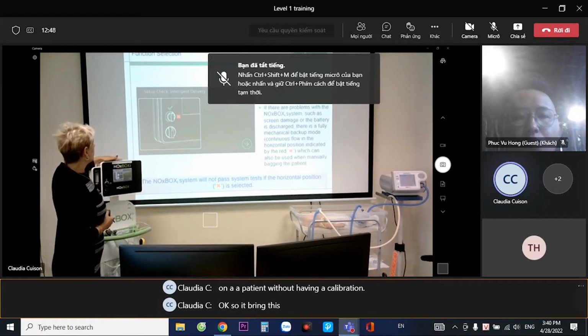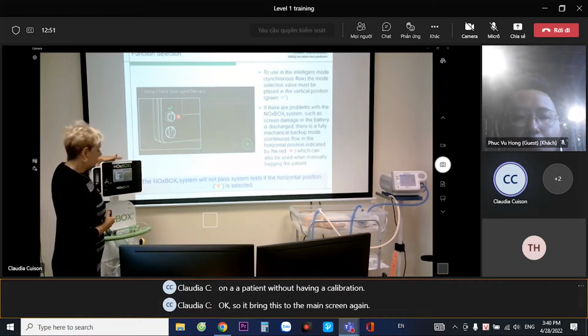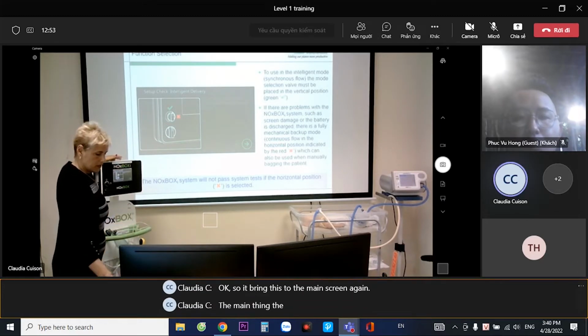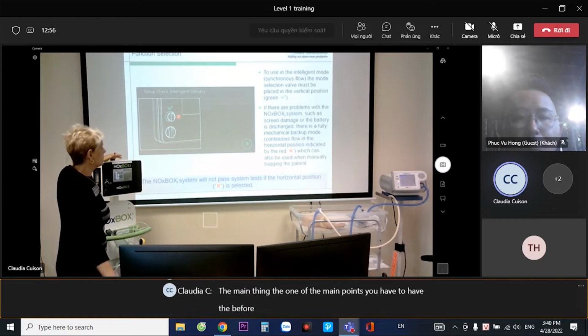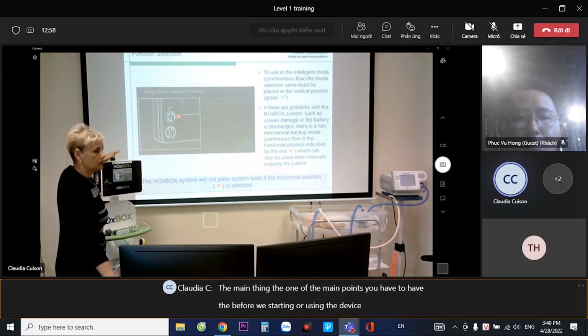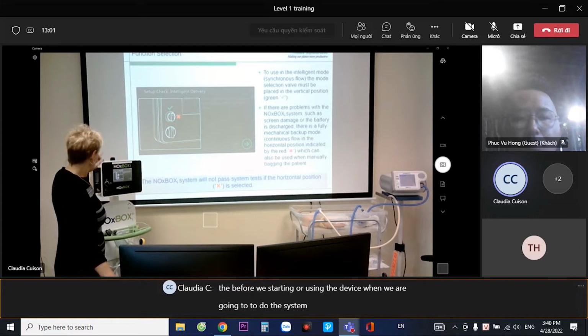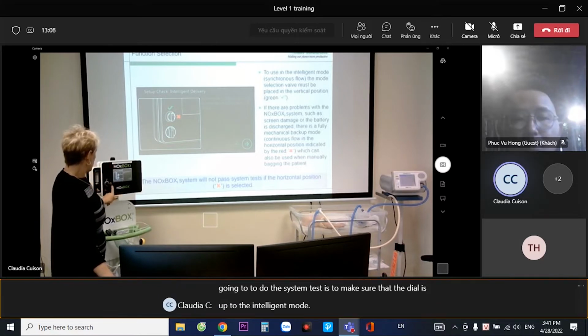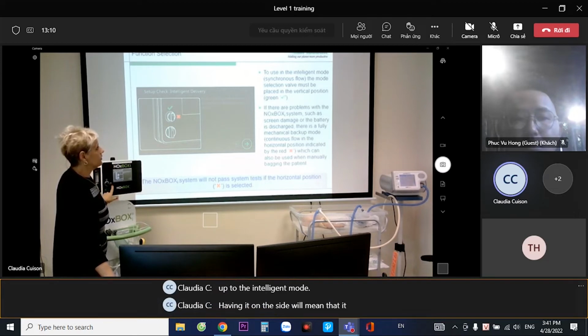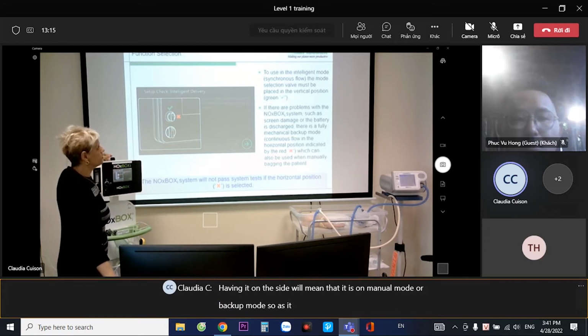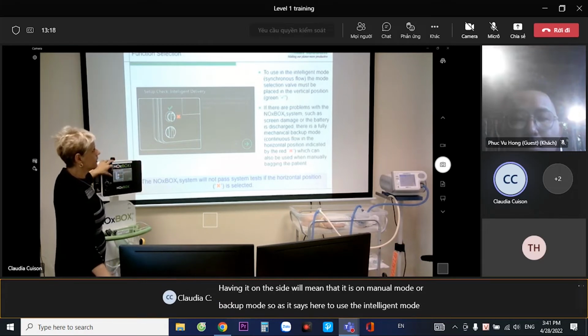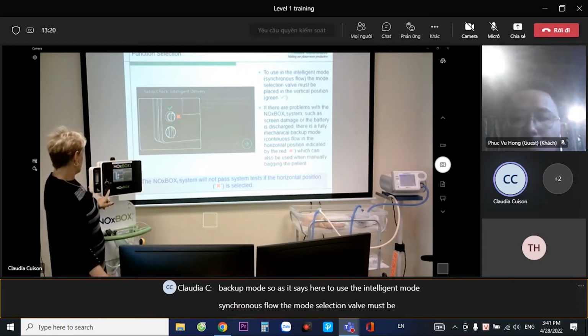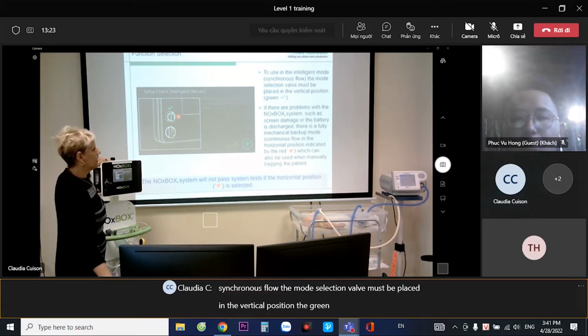Okay, so it brings us to the main screen again. One of the main points you have to check before using the device, when we are going to do the system test, is to make sure that the dial is up at the intelligent mode. Having it on the side will mean that it is on manual mode or backup mode. As it says here, to use the intelligent mode synchronous flow, the mode selection valve must be placed in the vertical position, the green.